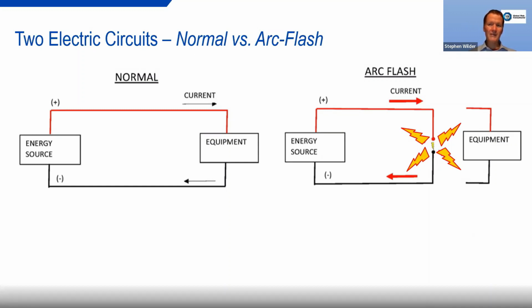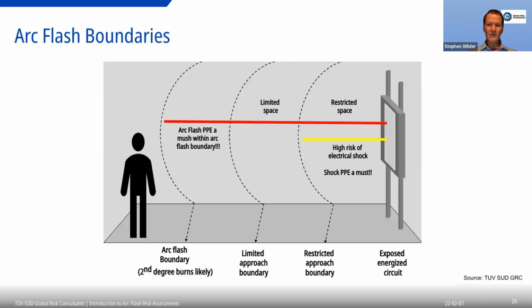Arc flashes have been around since electricity's been around. They were always considered something of a random event. People didn't know what to do about it, so they just kind of prayed that it didn't happen. But a few decades ago, there were some professors and some other experts who figured out how to model them, how to create a mathematical model for them. And since then, the regulations require that workers be protected from arc flashes. Engineers like me create the models and the calculations to determine how much energy can come out of each piece of equipment. When an electrician's working on that equipment while it's live, he could refer to the calculation I write to tell him how much energy that equipment can emanate. And based on this, he'll know what kind of PPE to wear.